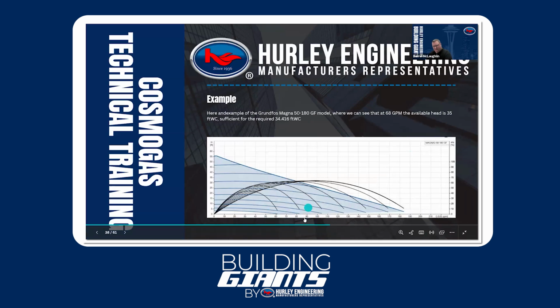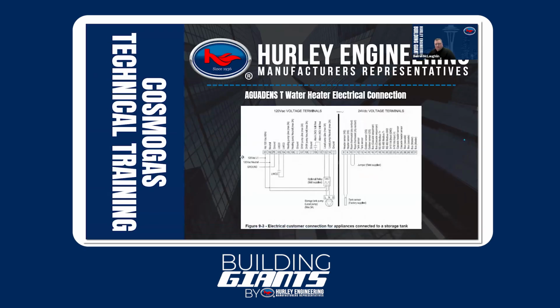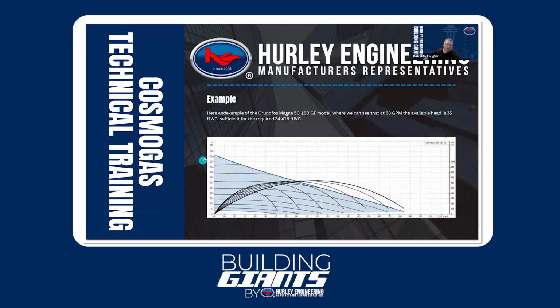And then just a curve, and I think we've all seen curves, but 68 and 35, and we just follow across, and then we pick the corresponding pump to match what we need. And this happens to be a Grundfos model. So that's the long and short of sizing pumps. That's the number one thing we've got to do with this equipment.